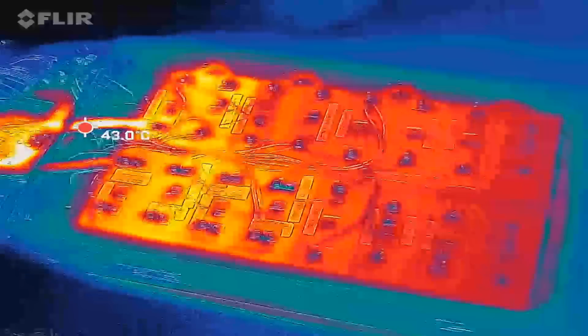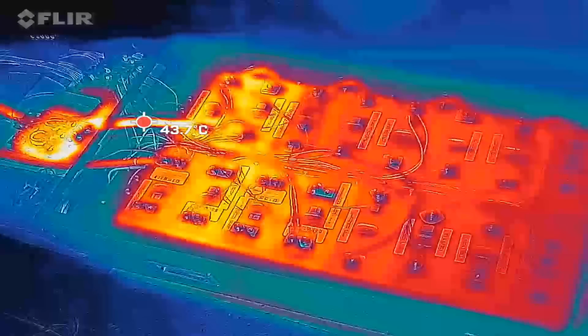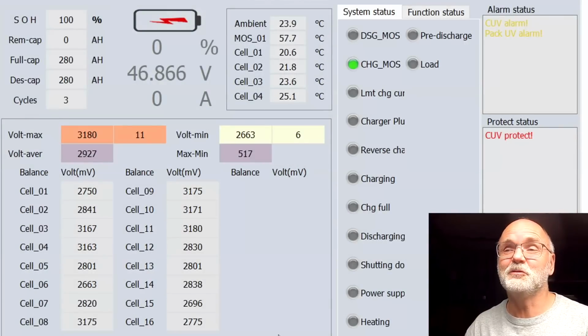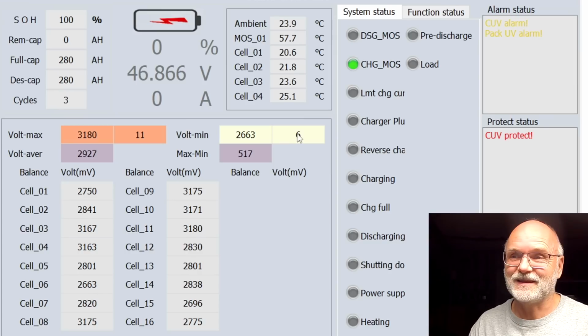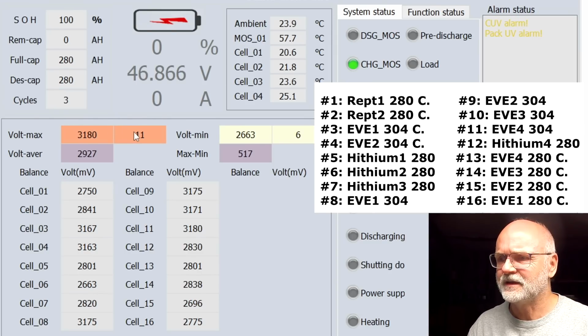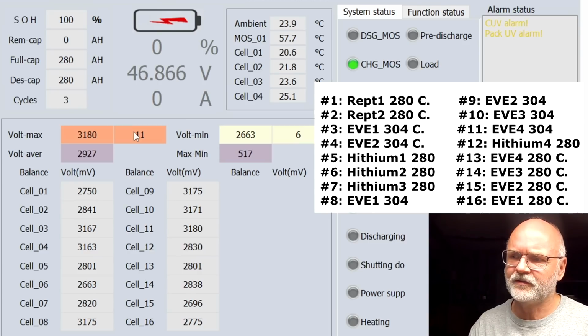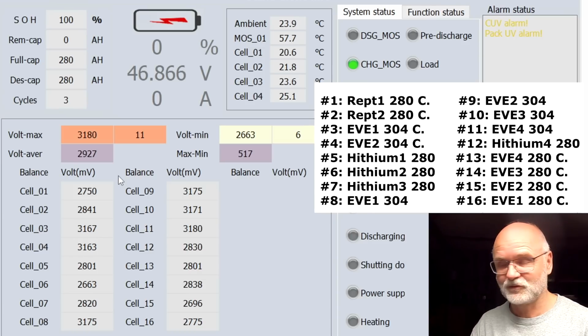But look at this battery, how good is it? Of course, we've got a huge deviation of 500 millivolt between cell number 6 and cell number 11. Cell 11 is the EVE 304 ampere hour, one of the oldies, bought in 2021. It is only cell number 1 and 2 which are the lowest capacity cells, and hence we are shutting down before we reach the 280 ampere hours. But apart from that, I mean, I'm super happy with the result.